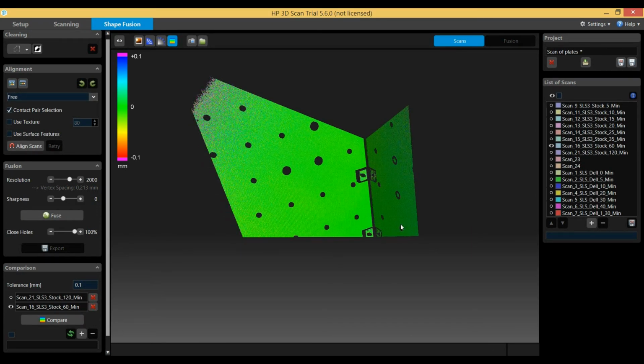For every guy out there who is still using that system, which is really still not bad actually. It's for a very reasonable price on the market. The resolution is not so small. Just one hint from that time when I was really getting angry quite a lot because of the results that didn't merge very fine: heat that system up, at minimum 45 minutes, then do the calibration.